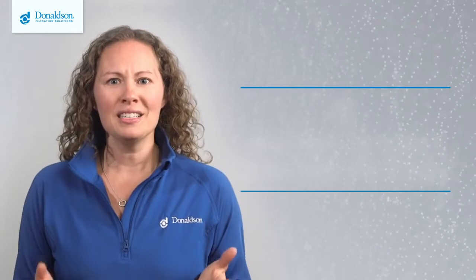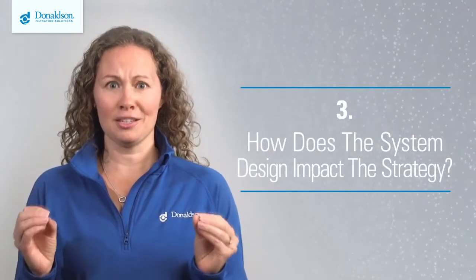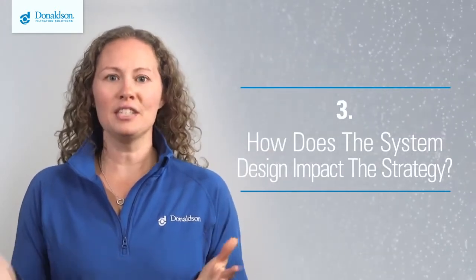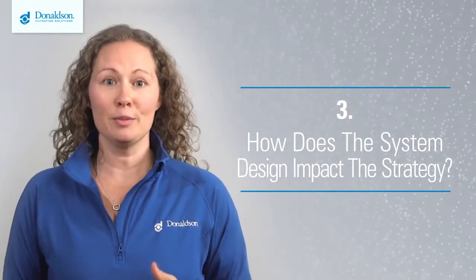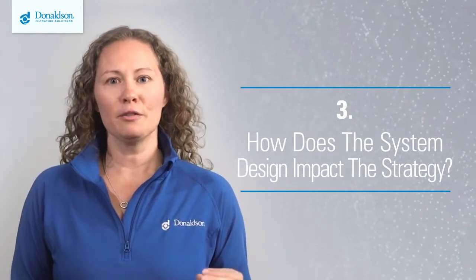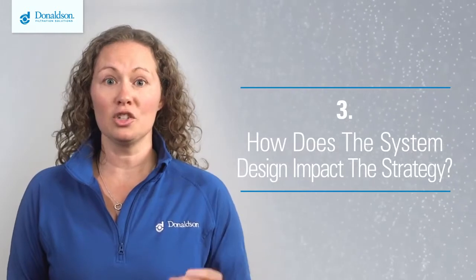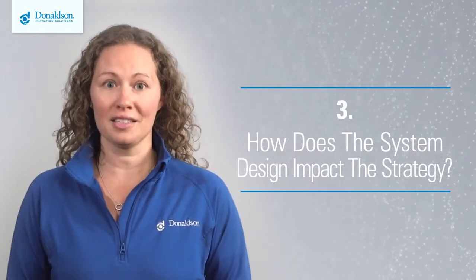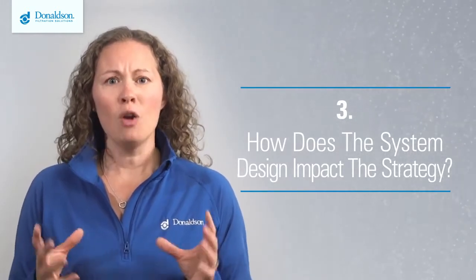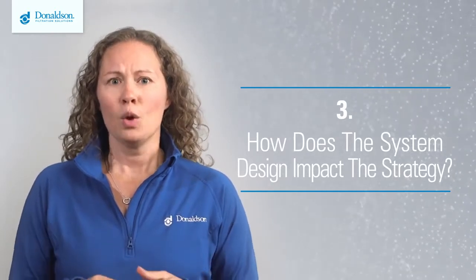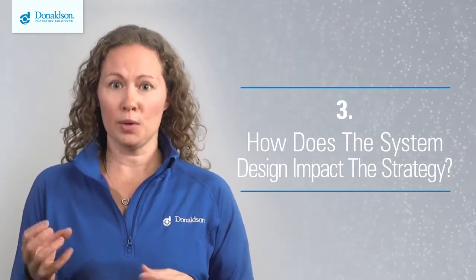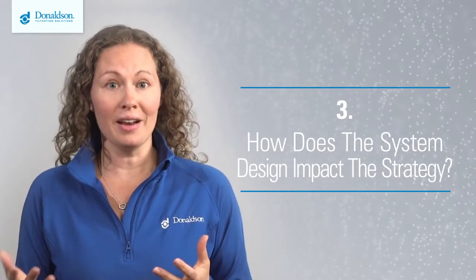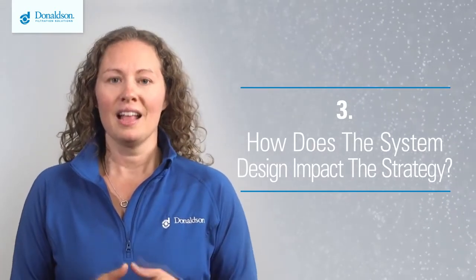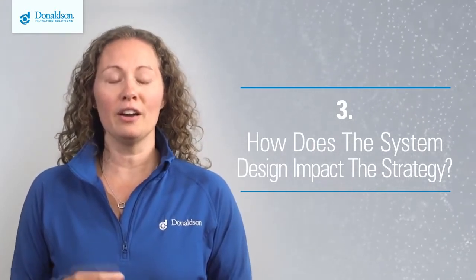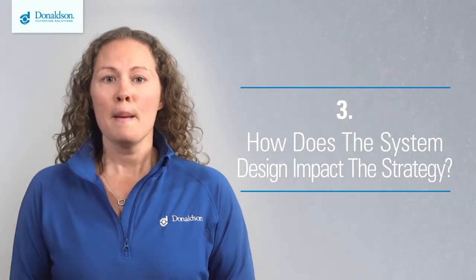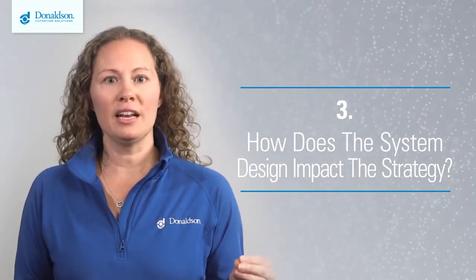Third, how does the system design impact the strategy? If you intend to return filtered air back into the building, you may need to consider fire and explosion isolation strategies on the return air ducts. In addition, how often your process operates will impact how quickly production lines need to be back up and running following an event.